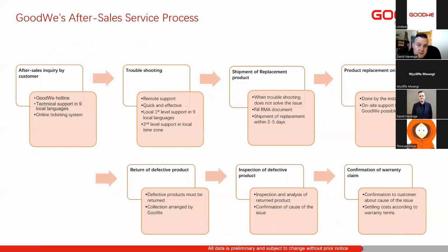So how does GoodWe's after-sales service work? We have an after-sales inquiry by a customer, either via our hotline, via our technical support online, or the online ticketing system. We then go through troubleshooting. We provide the troubleshooting steps and what the problems could be. We assess the data of the device online connected to the SEMS portal and offer that support back to the customer. Should that not be sufficient, we can then do a product replacement. In South Africa, we can ship a direct replacement to the customer, who can then replace it. In other countries, where we do not have local stock, you would normally approach your distributor and request a replacement from your distributor.